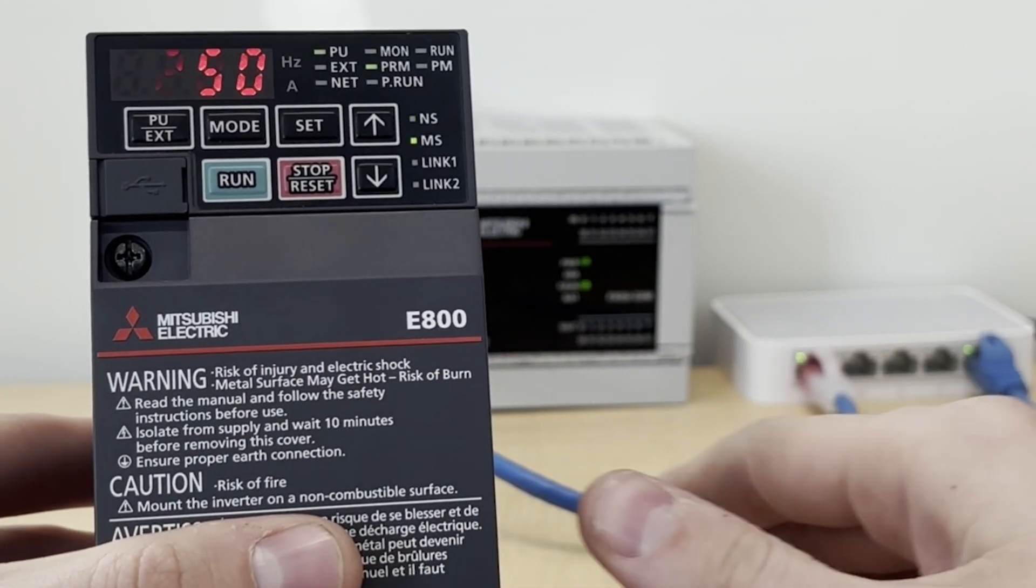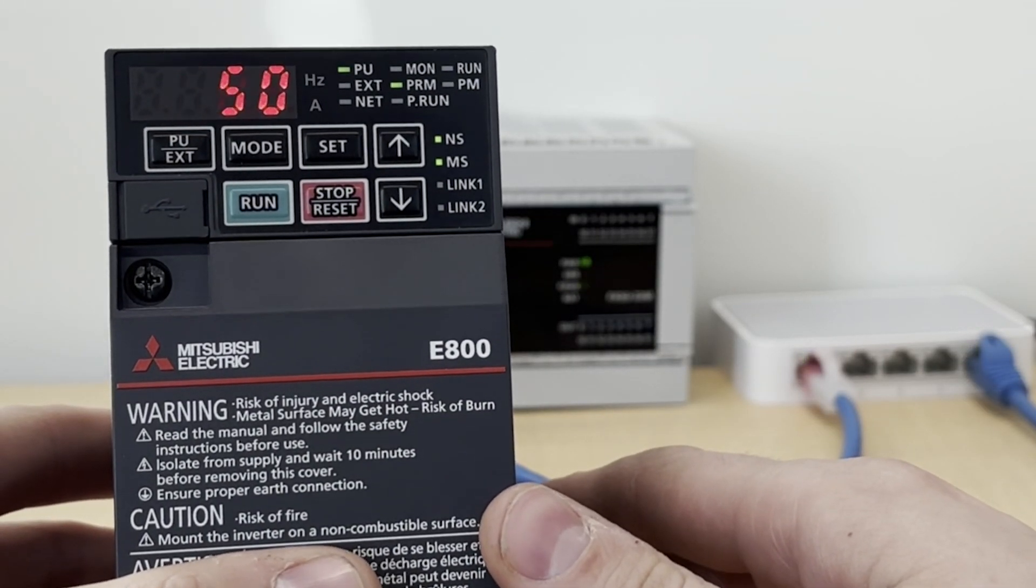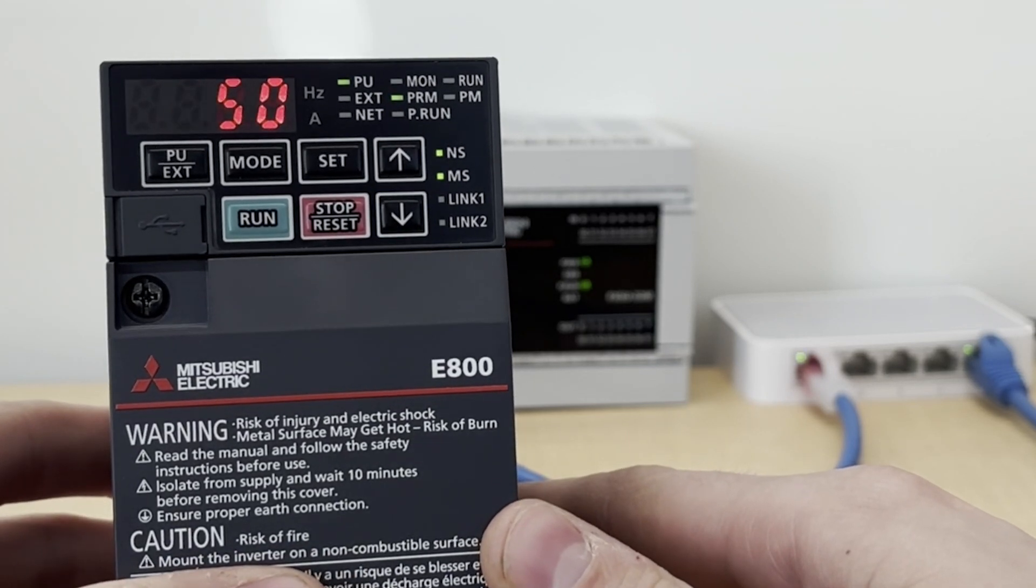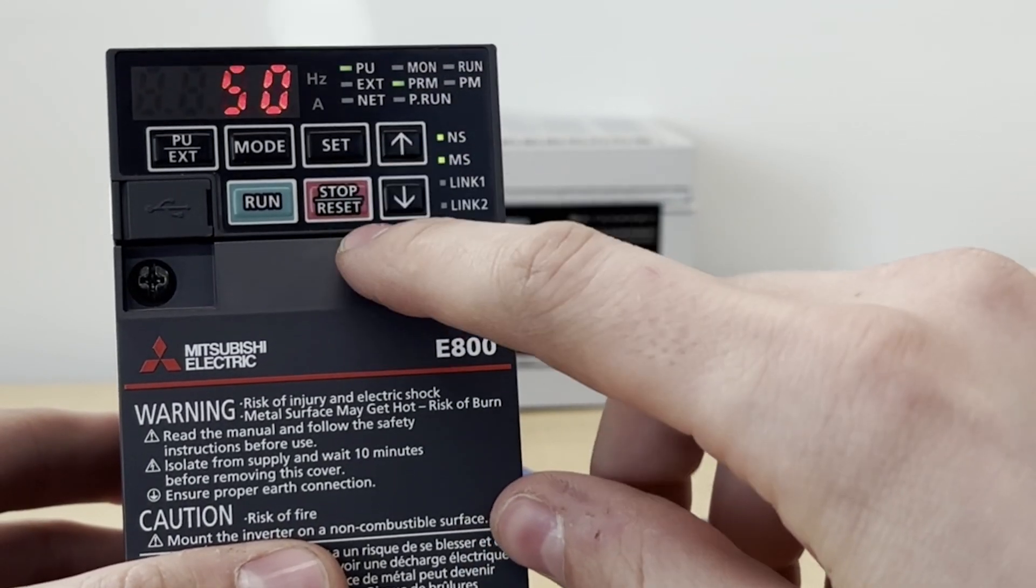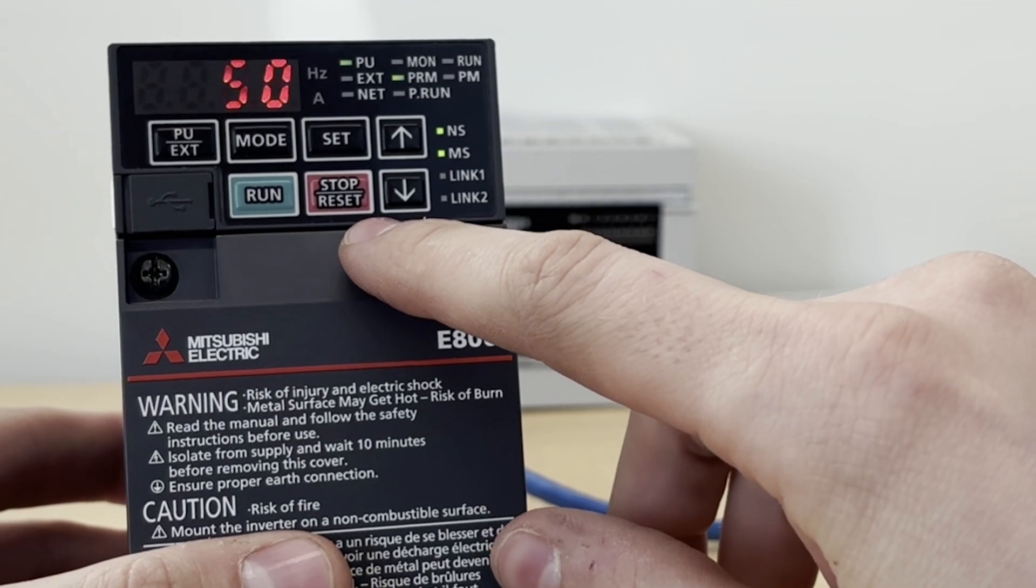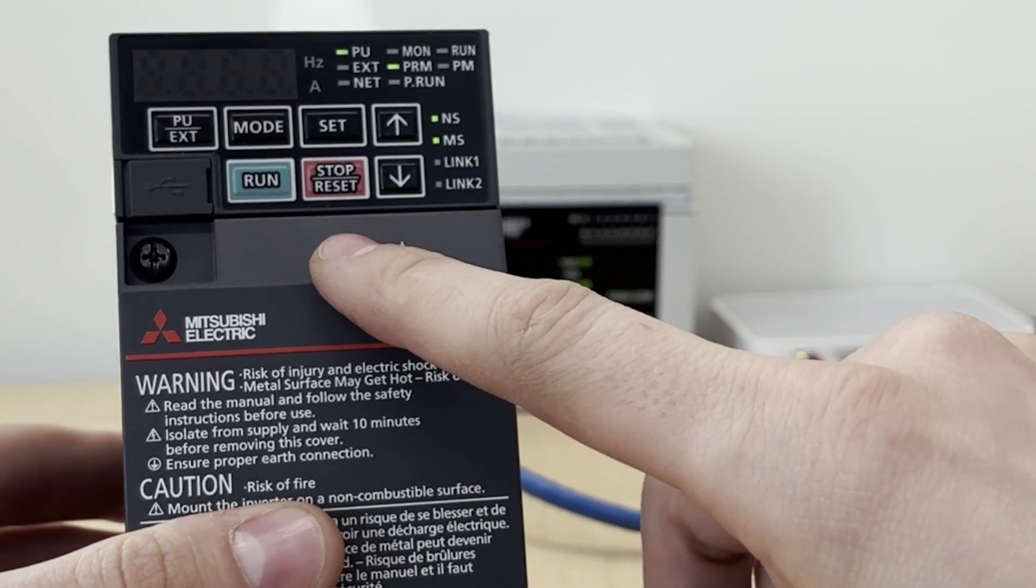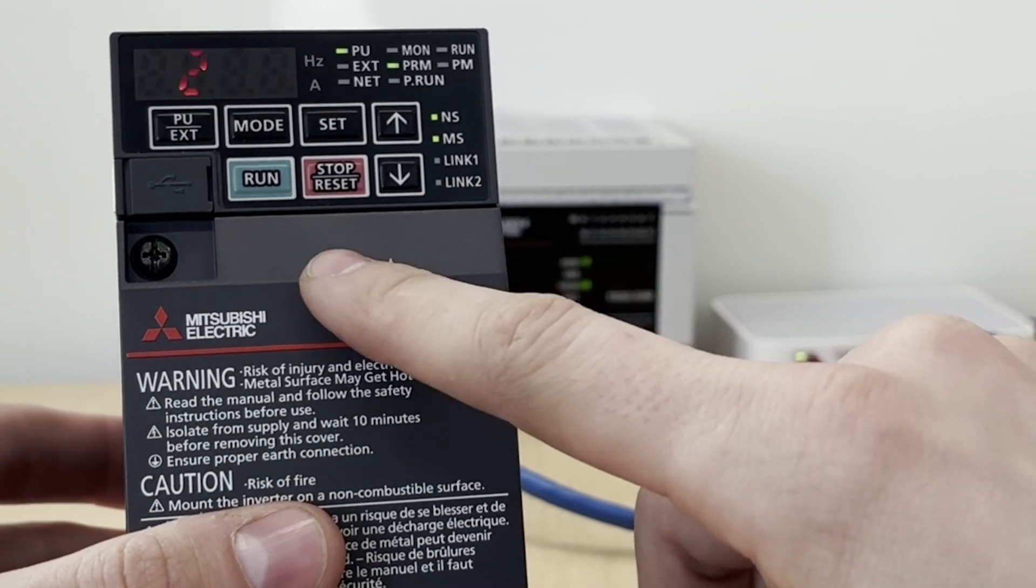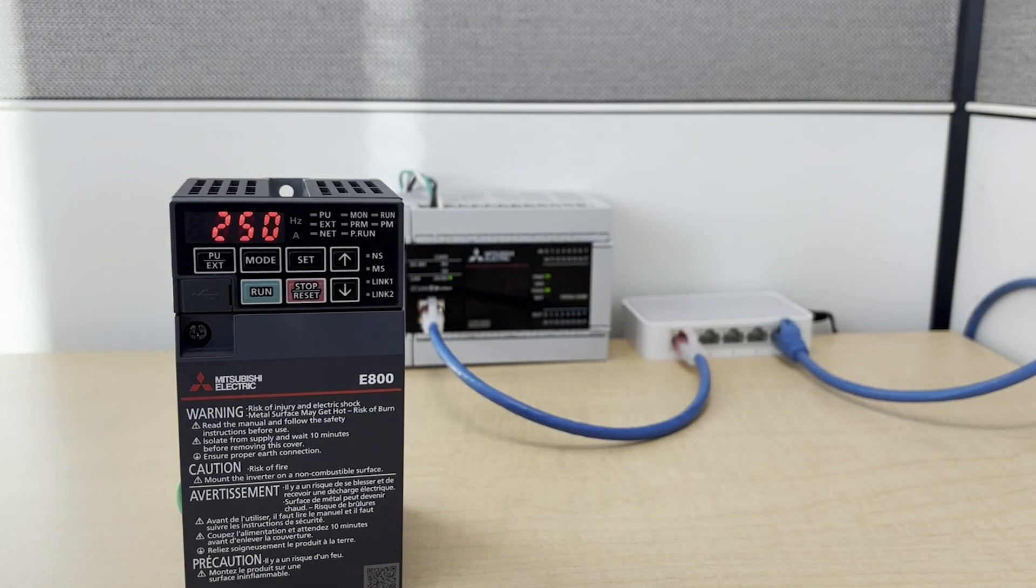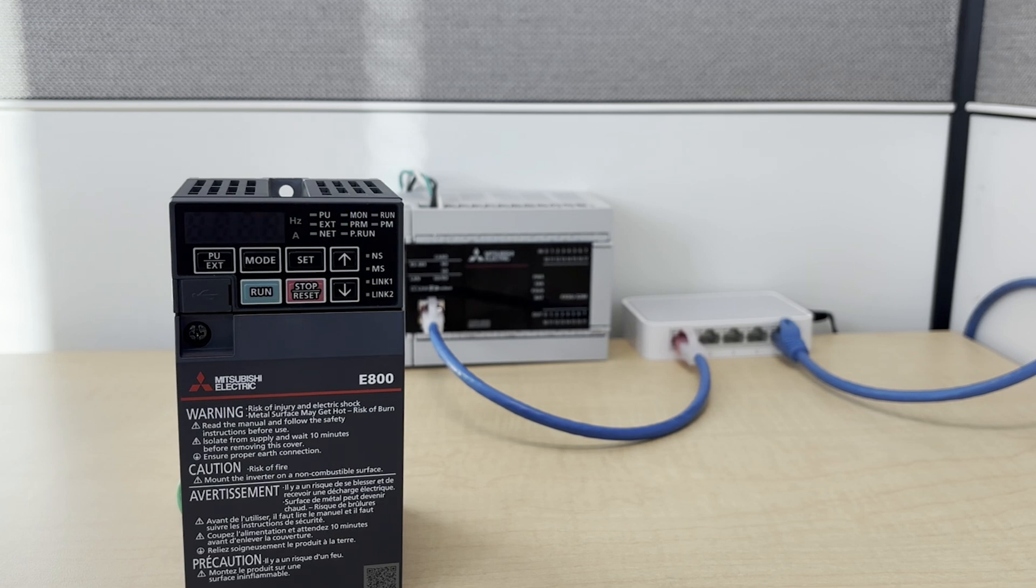Now that we've set those parameters, the next thing we need to do, and this is very important, is power cycle the whole system, power cycle the inverter, so that these parameters take into effect. They're not applied immediately when they're set. You have to power cycle before they will come into effect. So we're going to turn off power.